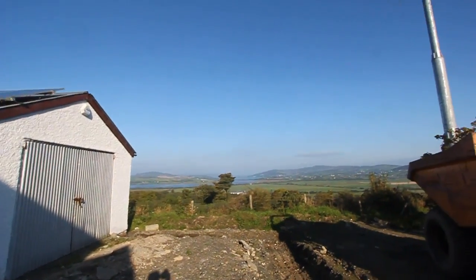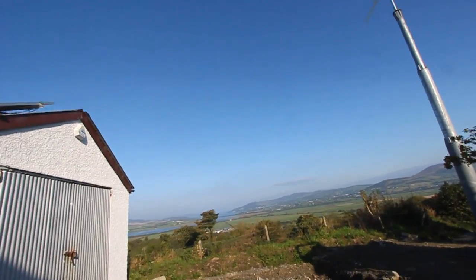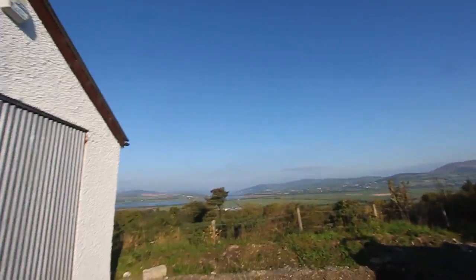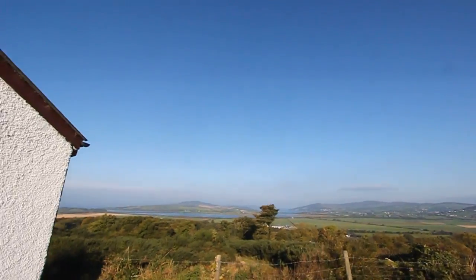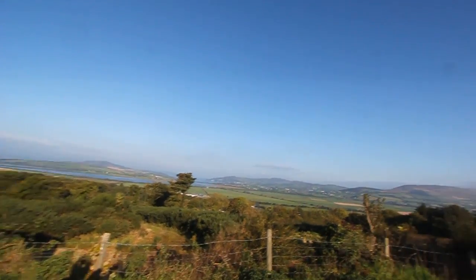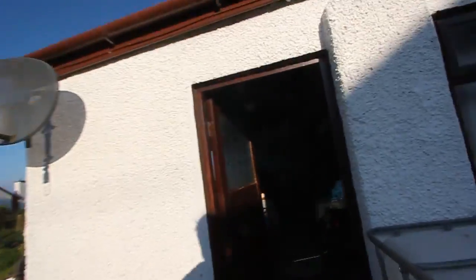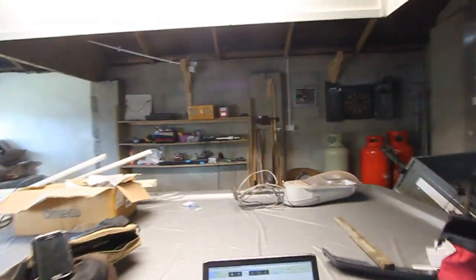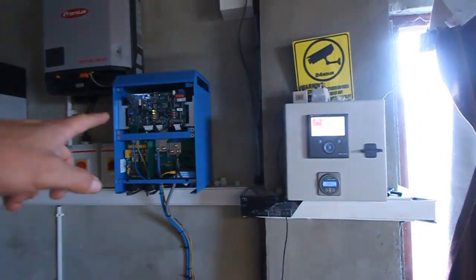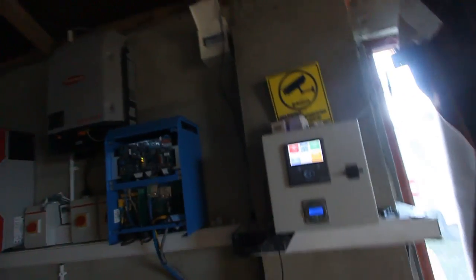And as you can see, this is Donegal, Northern Ireland, a very windy place. I wanted to avoid this because winter is coming, so I picked the stay connected to grid policy. And stay connected to grid policy in Hub 2 version 3 is not working very well because the Multiplus is taking power from the battery only when the load is higher than something like half a kilowatt.